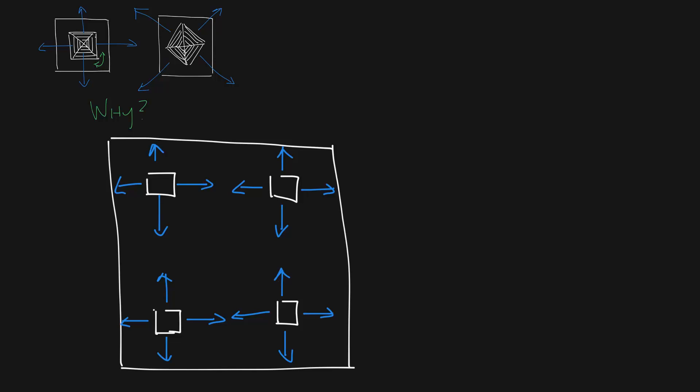So normally you would select the diffuser so that the air streams do not collide over 100 feet per minute velocity because if they do then the air will come down on the people in the space and cause drafts.